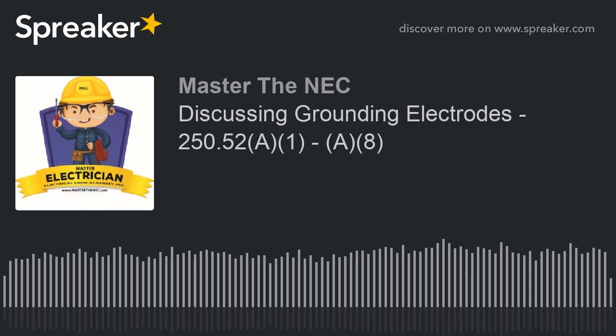Now, remember, we're talking about the grounding electrode system and the tying together of all of these electrodes that are present. It goes on to say, well, here's an exception. It says, concrete encased electrodes of existing buildings or structures shall not be required. So this is a permissive rule here. Shall not be required to be part of the grounding electrode system where the steel reinforcing bar or rods are not accessible for use without disturbing the concrete. So they're concerned about disturbing the integrity of the concrete. So it's not required for you to chip it up to get to it. And that would be for an existing building or structure.